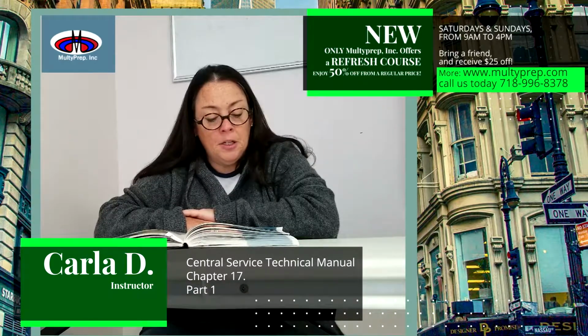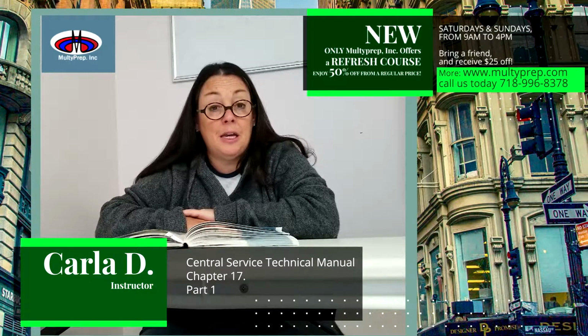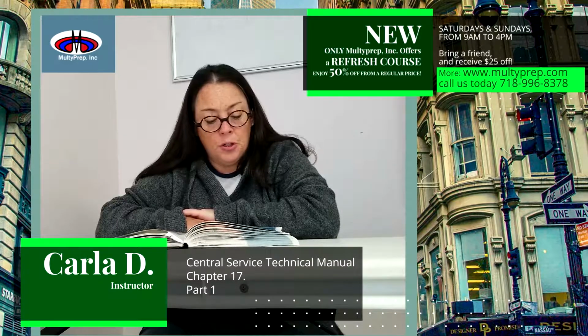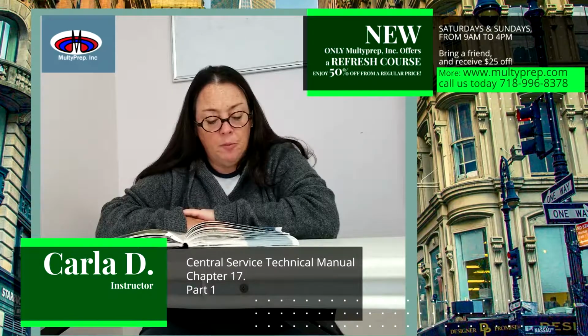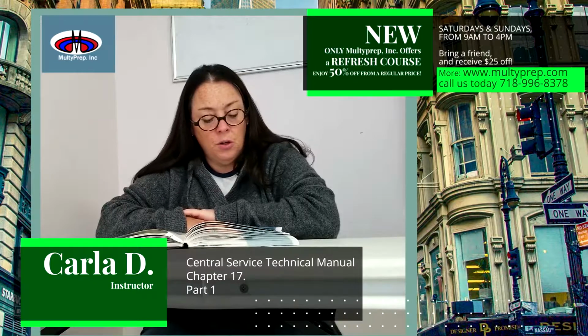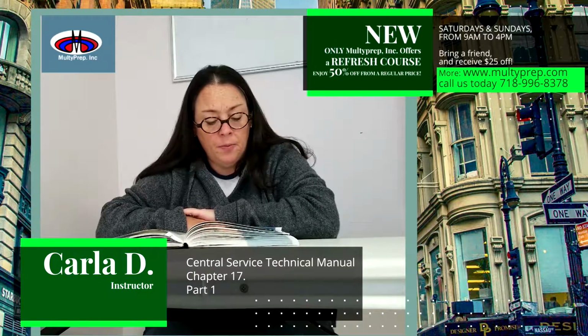ANSI/AAMI ST79:2013, the Comprehensive Guide to Steam Sterilization and Sterility Assurance in Healthcare Facilities, states: chemical indicators are designed to respond with a chemical or physical change to one or more of the physical conditions within the sterilizer chamber. There are two basic types of process indicators: internal chemical indicators, CIs, that are placed inside a package to be sterilized, and external CIs that are placed on the outside of the package.